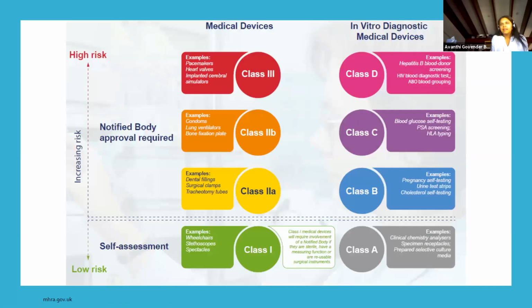As a complexity, the EU, as you would know, in 2017, changed their regulations to ensure that they have more oversight on medical devices. So what you see is a system that they've put into place, and I'm not sure if you see my pointer, they have the class 1, 2A, 2B, and 3 system for medical devices. And in the IVDs, they stuck to the A, B, C, D system of the IMDRF. Again, this moves in increasing risk, where class 1 is a very low risk device, and you move on to 2A, 2B, and class 3, where it becomes an increased risk to person and public, but also requires more regulatory oversight. And this applies to both medical devices and the IVDs.